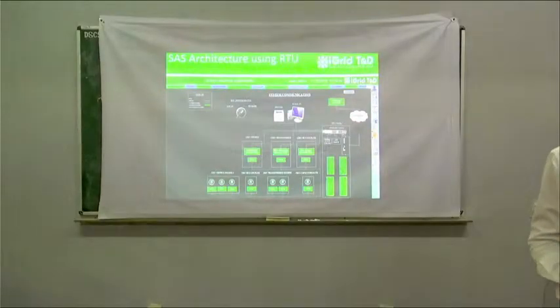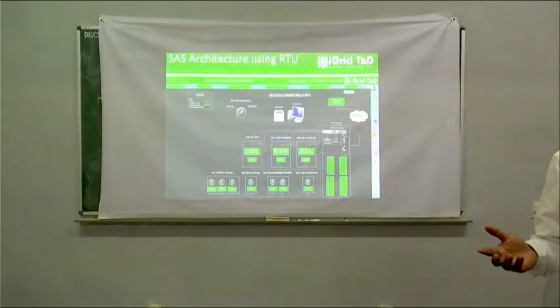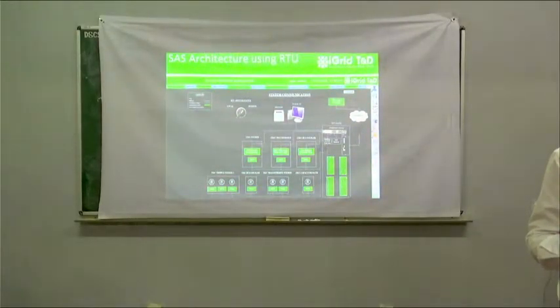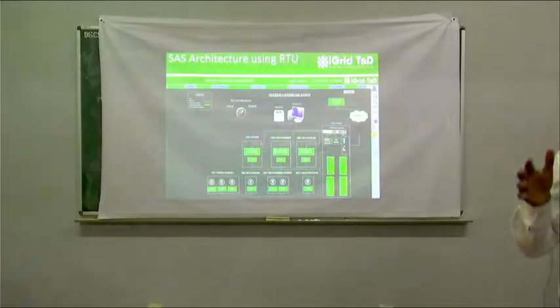Why do I require an RTU? Say for example, I have an old substation where I don't have any communicable relays. So I don't know the status of my breaker, or maybe I want to know the status of my master trip relay, or the status of my trip circuit supervision relay. In those cases, in the legacy substations, we provide them with this RTU panel.